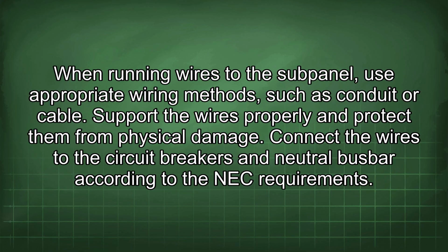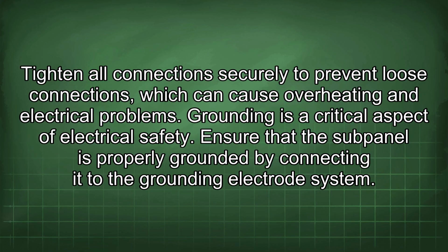When running wires to the subpanel, use appropriate wiring methods, such as conduit or cable. Support the wires properly and protect them from physical damage. Connect the wires to the circuit breakers and neutral busbar according to the NEC requirements. Tighten all connections securely to prevent loose connections, which can cause overheating and electrical problems.